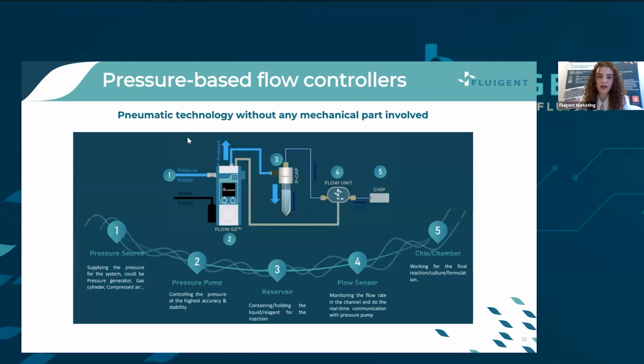So what is the technology behind our pressure-based controllers? It is a pneumatic technology, so we don't use any mechanical part within the system. As you can see here, we have our pressure pump here, which will be connected to a power supply, and it will be connected to a pressure supply. So this pressure source will supply the pressure for the system. It could be, of course, the pressure generator, gas cylinder, compressed air. The pressure here will be regulated by our pressure pump and injected inside a very well sealed reservoir containing the liquid of your choice, for example, cell culture media.